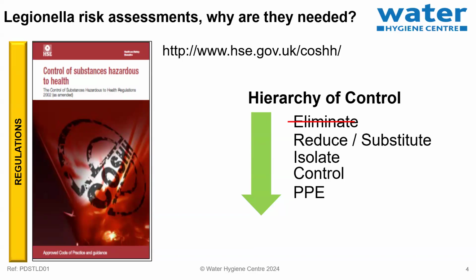So, for example, no overstored capacity or reduction in the amount of aerosol generating systems that we've got on site, or try to mitigate any dead legs or low flow areas or infrequently used areas or blind ends. And to ensure that we've got good control through temperature or supplementary control that can actually add to the control procedures in place. But with all of those things in place, we also need a management plan.